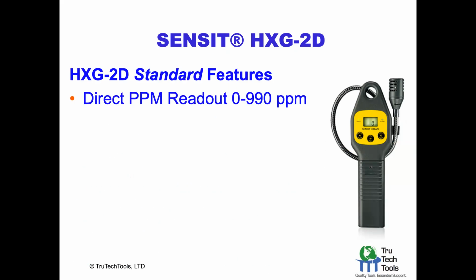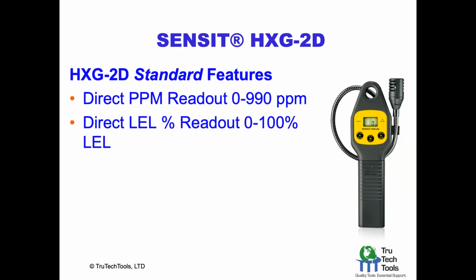It has a direct readout of ppm, parts per million. Now, this is not a carbon monoxide analyzer. This is a gas leak detector and a gas concentration meter. So it's actually measuring ppm of gas. And that's a little bit different. We'll talk about what that actually means. What is ppm when you're coming to gas, and what does it have to do with the explosive concentrations?